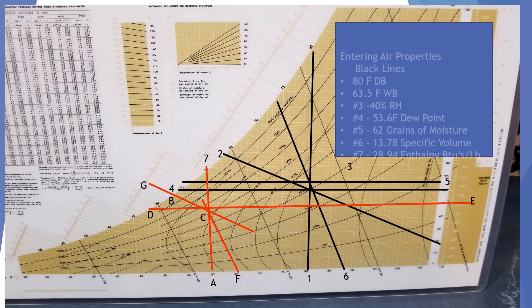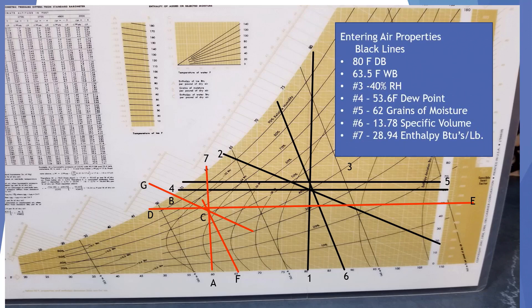By plotting various points on the psych chart, we can tell the property of entering and leaving air. In this plot, we are looking at the entering air properties, which are the black lines. We have 80 degrees, which is our dry bulb temperature. We have a 63.5 wet bulb temperature. At number 3, we have 40% relative humidity.